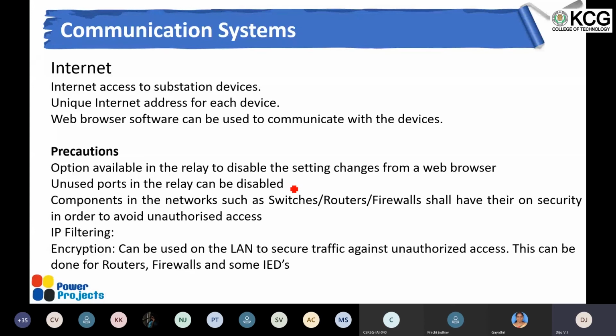And we also need security for each and every component in the network, which generally comes by default. We can have some IP filtering, so that only particular IPs are able to enter the network. Then encryption is also possible, so that nobody can send traffic, I mean data, into the network. It needs to be encrypted before it is sent, and once it is received by the IED, it checks whether the encryption is correct or not, and only then does it take any action. So these are the ways security threats can be handled by the industry.